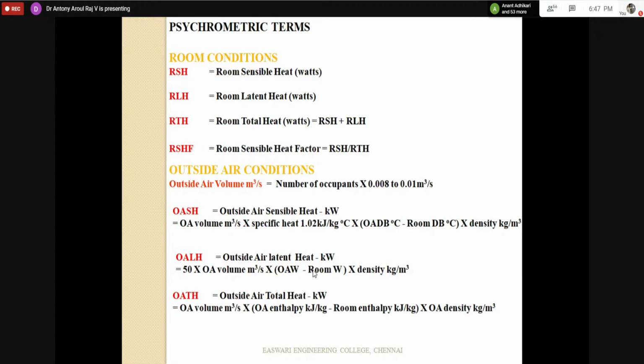So how to remove the moisture from the air? That means I have to condense this air. This condensation will take place in the cooling coil, because the cooling coil temperature will naturally be less than the dew point temperature. Because of that, the moisture will settle on the surface of the cooling coil, and the moisture will be removed. But for that, we have to take all these things into the load calculation.